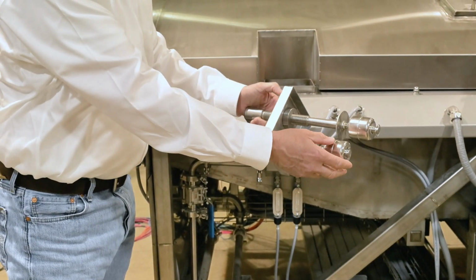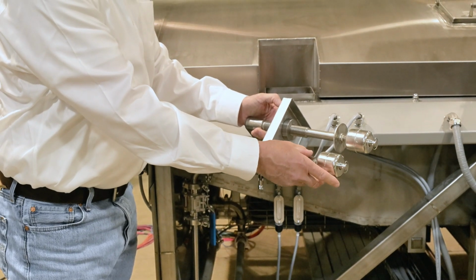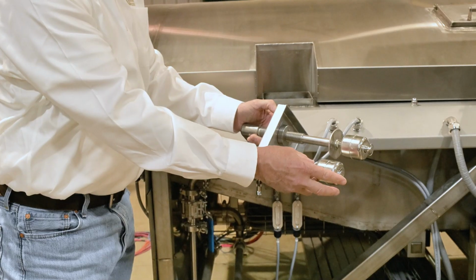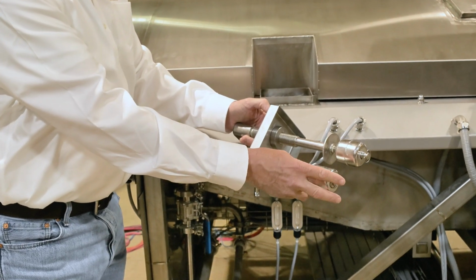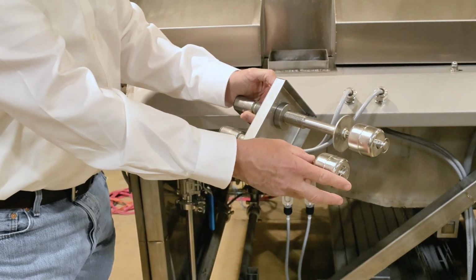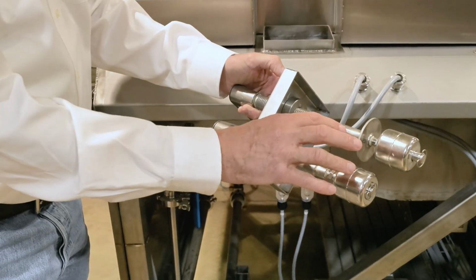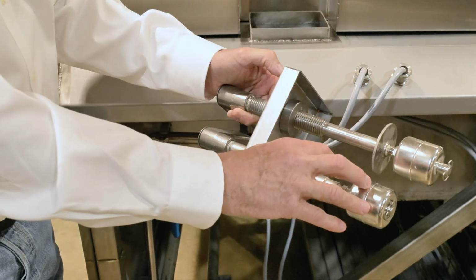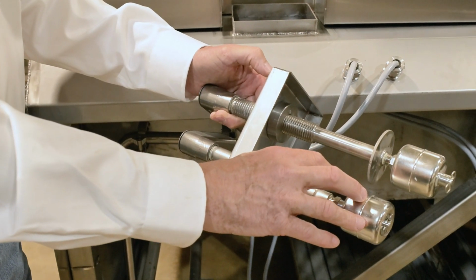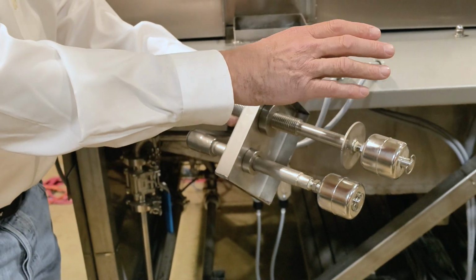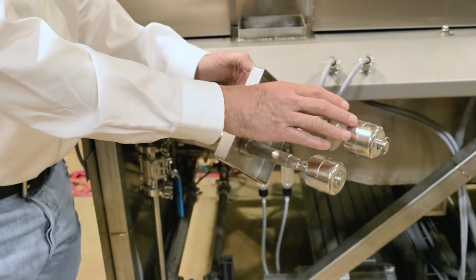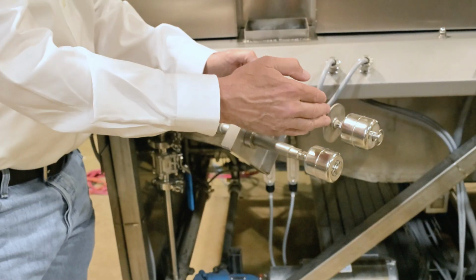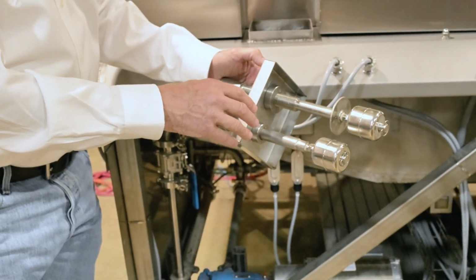And this is the non-adjustable float that allows us to turn the pump off when it reaches height or on when it's too low. This float turns the pump on when the oil level is too low. This float is adjustable and turns off the pump when the oil level reaches the set point.